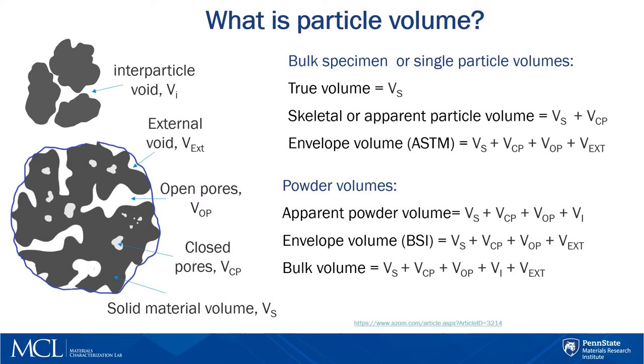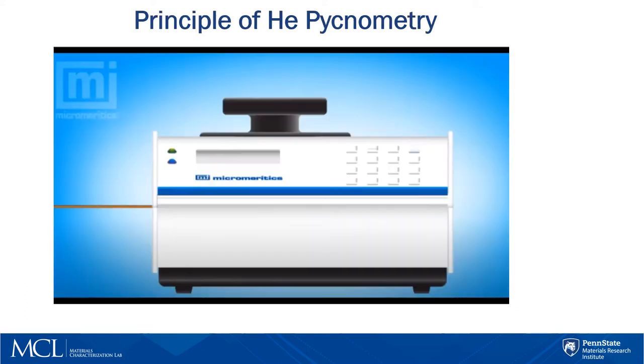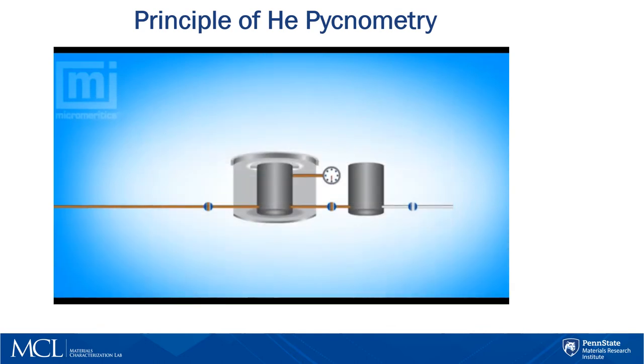Helium pycnometry measures particle skeletal volume, which includes material volume and also the volume of closed pores. Helium is typically the gas of choice because it easily diffuses into small pores. The helium pycnometer works by measuring the amount of gas displaced by a sample.